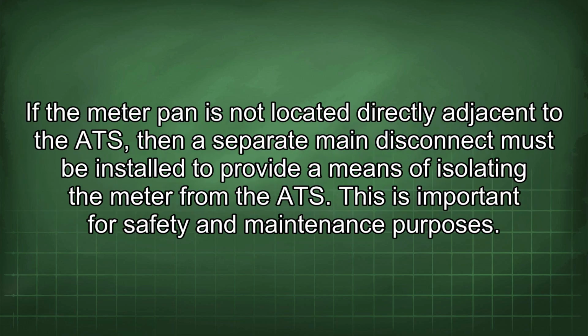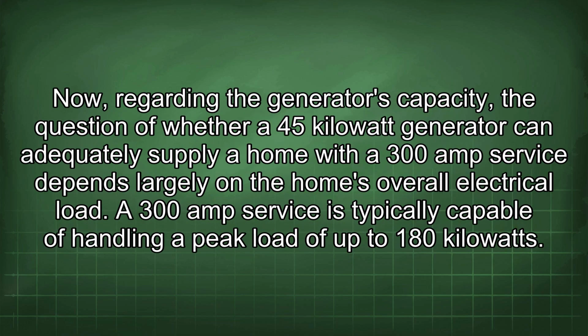If the meter pan is not located directly adjacent to the ATS, then a separate main disconnect must be installed to provide a means of isolating the meter from the ATS. This is important for safety and maintenance purposes. Now, regarding the generator's capacity, the question of whether a 45 kilowatt generator can adequately supply a home with a 300 amp service depends largely on the home's overall electrical load.